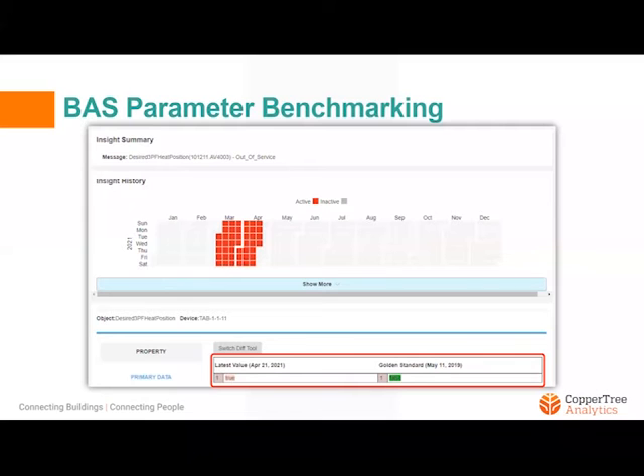And whenever there is a change in object property values, the tool can trigger an insight saying, hey, for this particular controller, for this particular object, in this case, an AV, this particular property, out of service, there is a change. What is the change? Well, the golden standard from 2019, May 11th, was that the out of service property was false, but now the out of service property is true. And all of a sudden, the change, in this case a bad change, is flagged, alerted, and the building operator can take care of the issue.